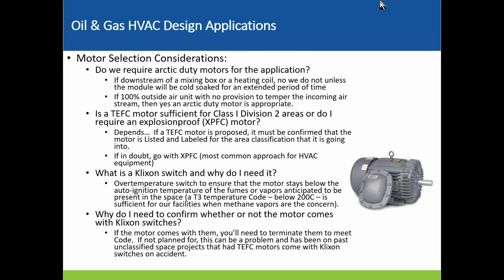Why do we need to confirm whether the motors we're getting from our air handling unit supplier or our pump supplier are coming with these Klixon or over temperature switches or not? There's a lot of confusion, especially with air handling units, where even though we're putting something in, let's say, an unclassified module or a control room, we don't want the over temperature protection. A lot of our vendors won't know the difference because we're doing process modules alongside our non-process modules, and then we'll end up with a motor with Klixon switches on it, and then it has to be wired in, but there's nowhere to land the wires.